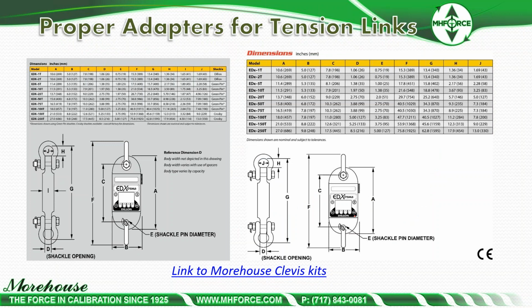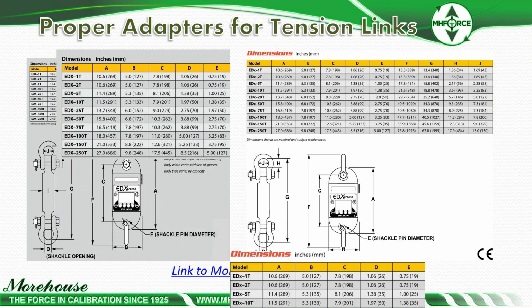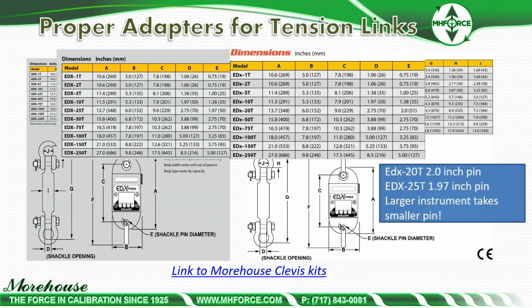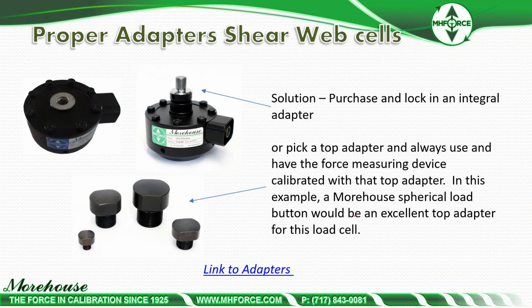Here's a good instrument for weighing. But if we start looking at spec sheets, we're looking at a 20-ton takes a 2-inch pin, and a 25-ton takes a 50 millimeter, 1.97-inch pin. And you could say there's not much difference between 2 inches and 1.97. I will tell you that it is enough to put the instrument out of tolerance. Probably not your 1.72% error, but it's certainly enough to have 20 or 30 pound error, which on a 50,000 pound device could kick the device out of tolerance when it's actually in.